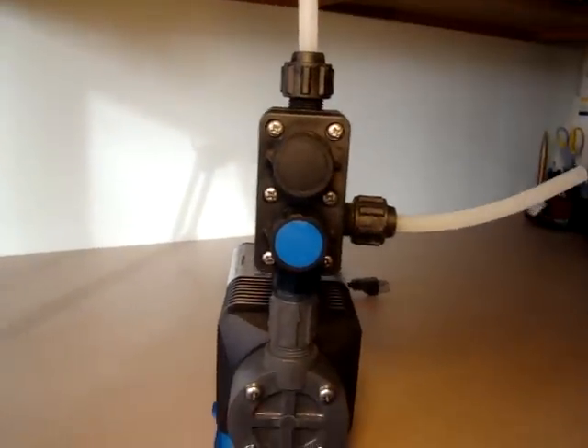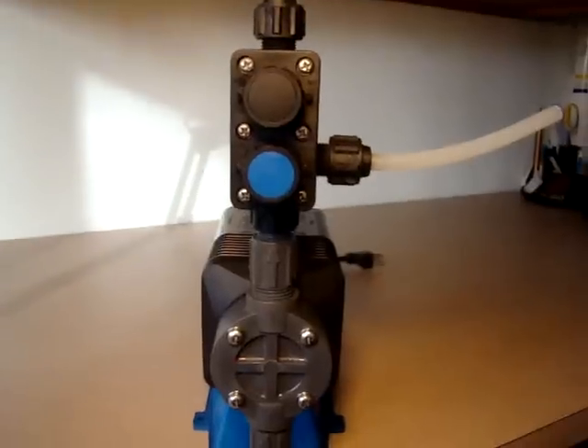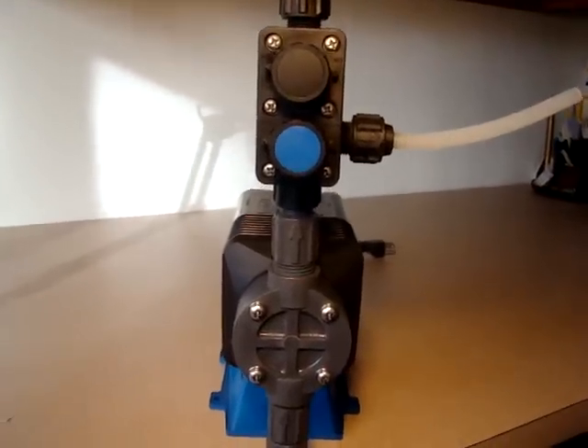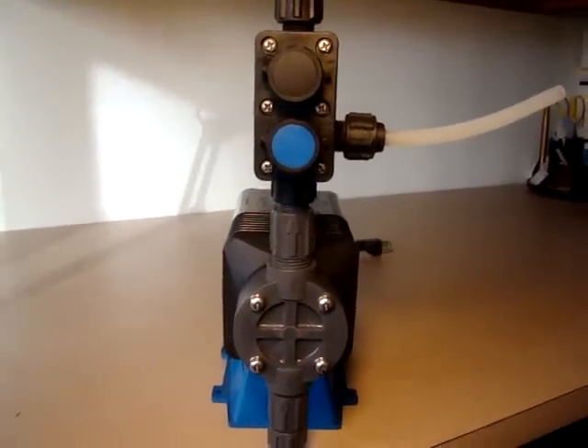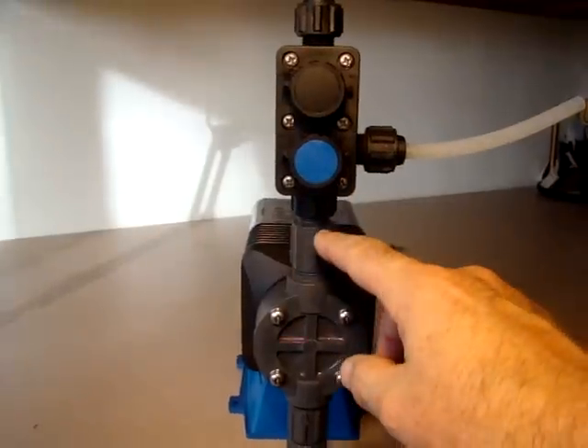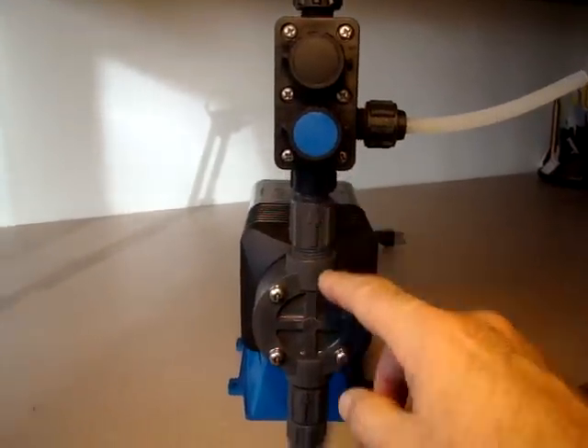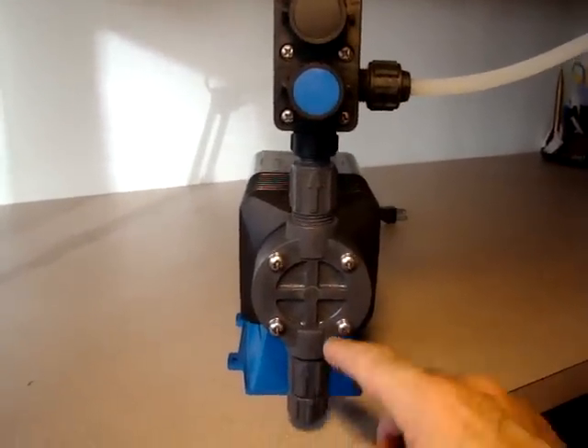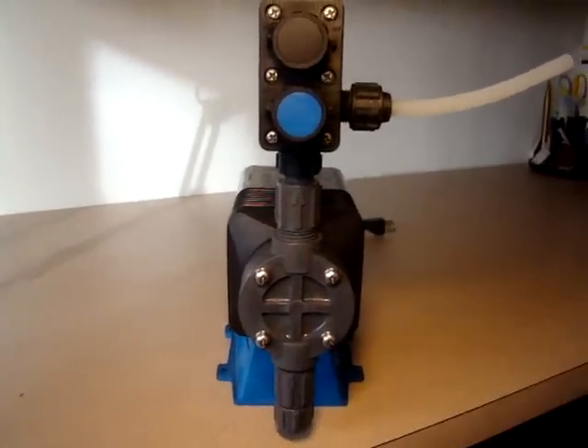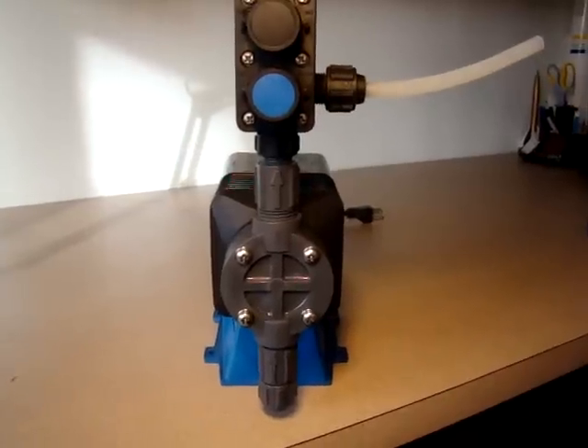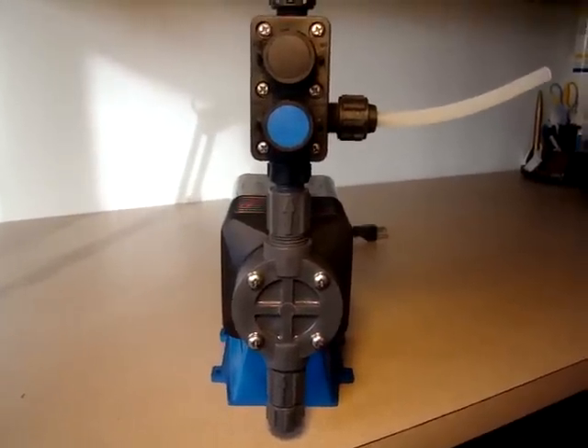If you don't have pulsing, then more than likely you have to go on to some other possible reasons for the pump not to be pumping. The next most common reason for the pump not to pump is that in each of these connections right here, there are check valves which will need to be cleaned. That process gets taken up in another video. There you are.